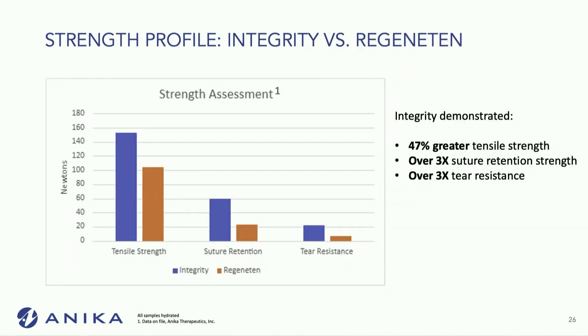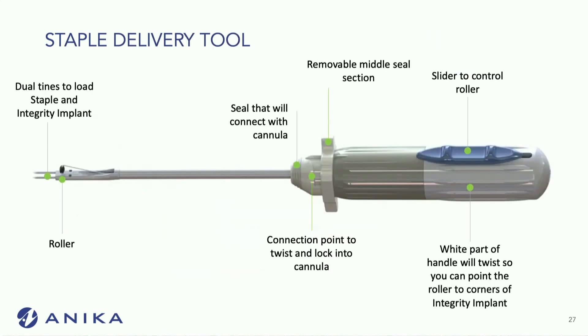Head-to-head, we compared these two implants, and the tensile strength was much higher — over three times more suture retention strength and tear resistance compared to the Regeneten patch.